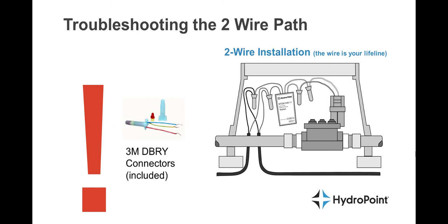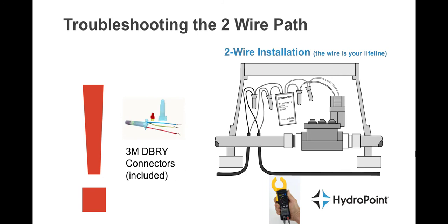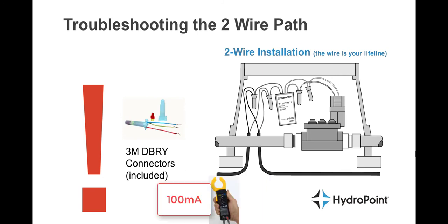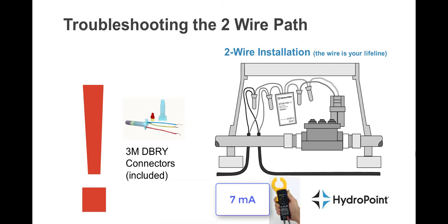Here is how you know if you found something. With the short finding mode on, any piece of wire that is before the short will have a very high milliamp reading. Any piece of wire that is after the short will have a very low milliamp reading. So if coming into a valve box you have a hundred milliamps, and going out of that valve box you have seven, that is a significant change. That difference indicates there is a short in one of those components or connections.